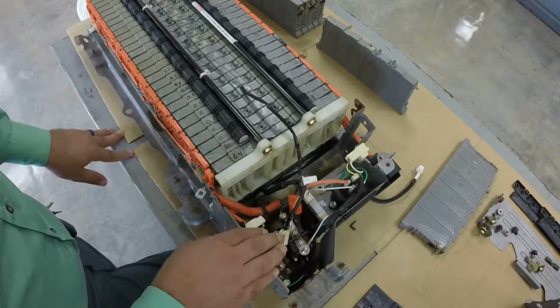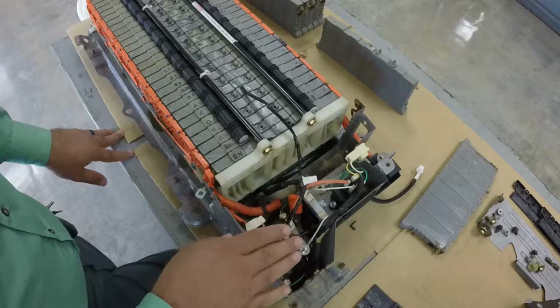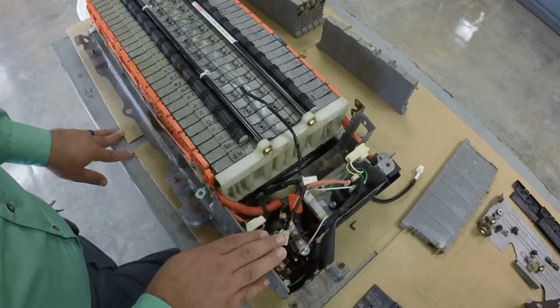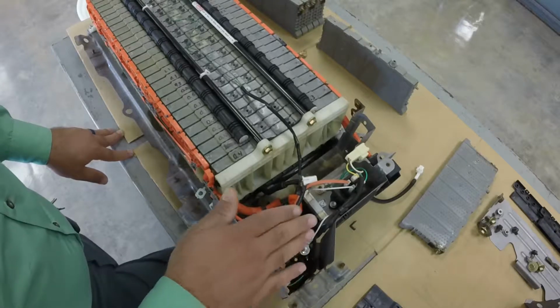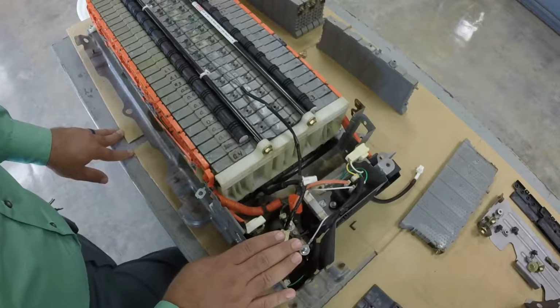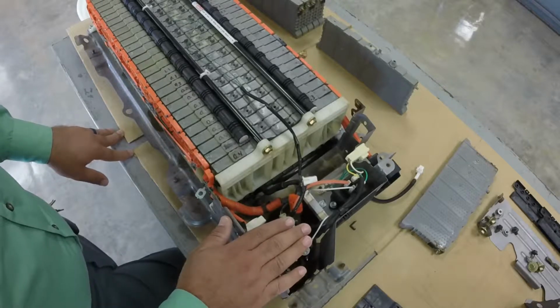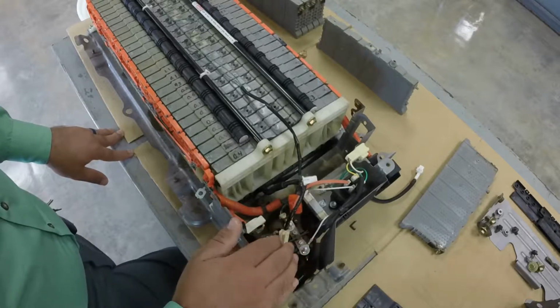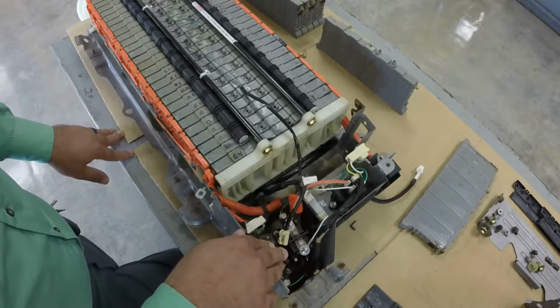So it's going to turn on one relay first, check for isolation, then shut that relay off. It's going to turn the second relay on, check for isolation, and if that test passes, it will leave that relay on and turn the first relay back on.